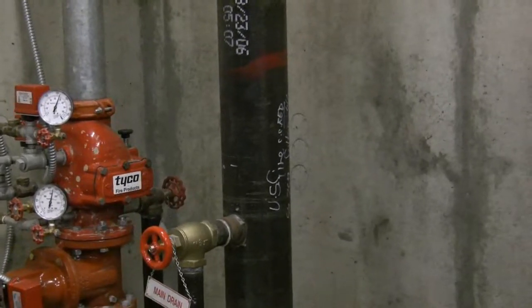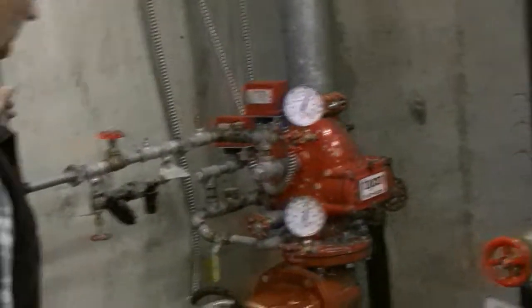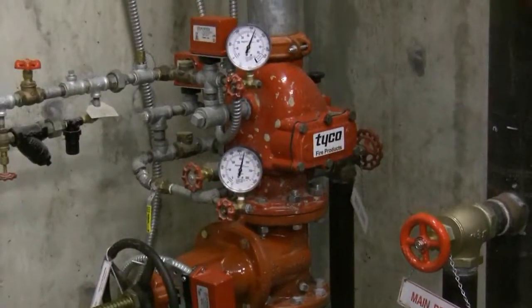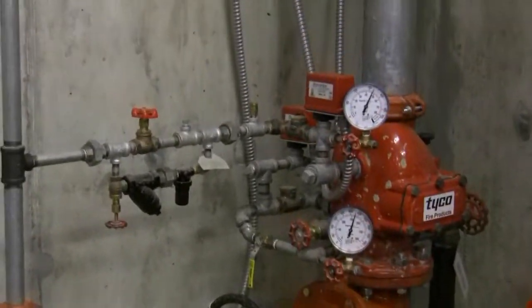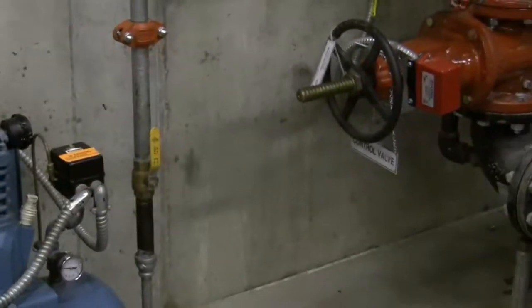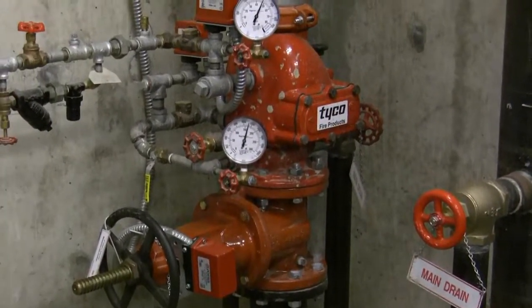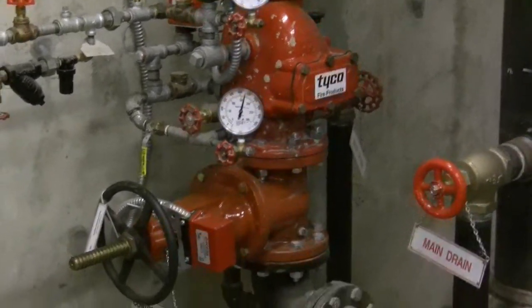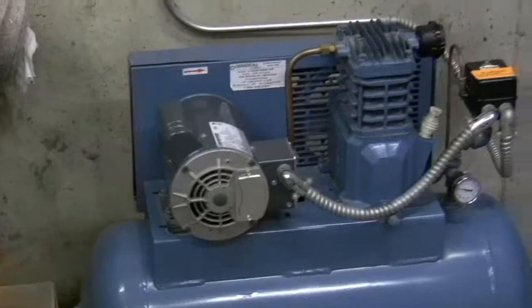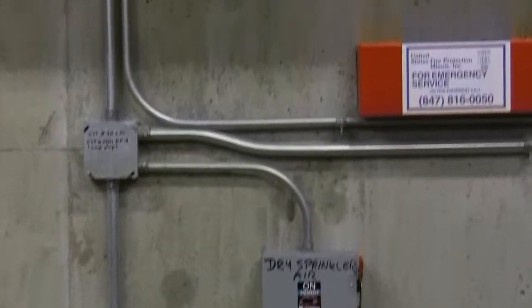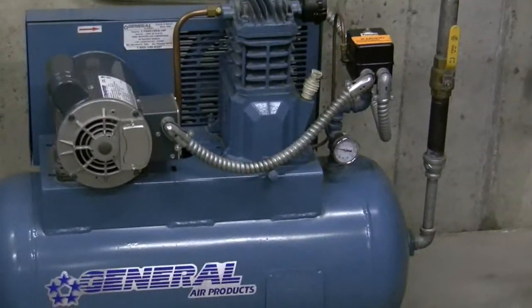Do you want to point out which is which here? Okay. Obviously this is the main pump. This system over here that goes to the lower level of the garage is the dry sprinkler portion of the system. The reason for that is it's capable of standing below freezing weather. This air compressor is marked dry sprinkler air, and it's very important to maintain the pressure in the dry system so that water does not flow through it.